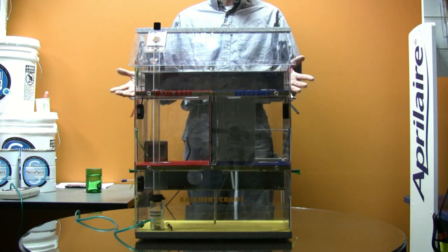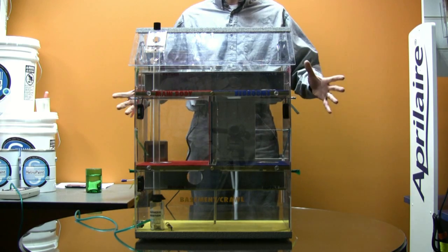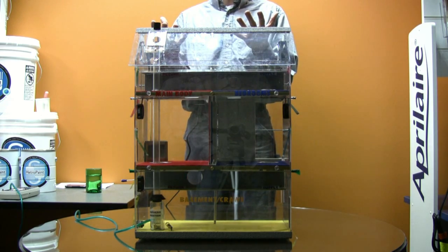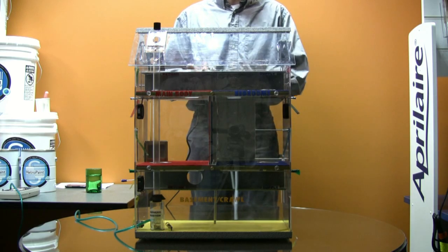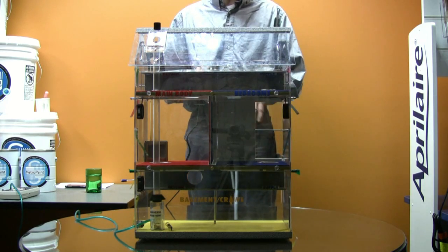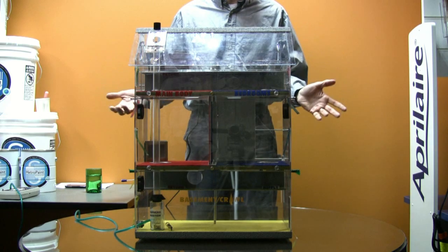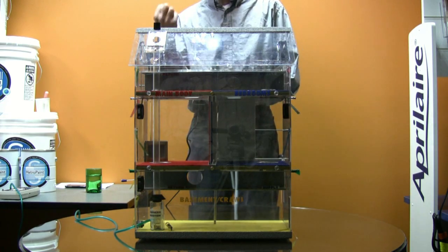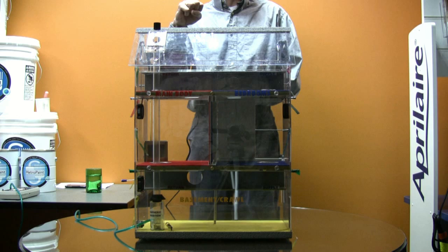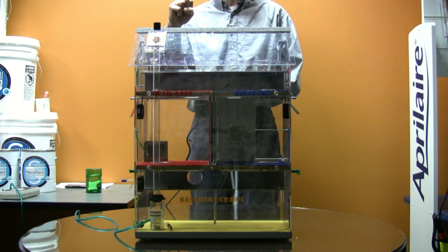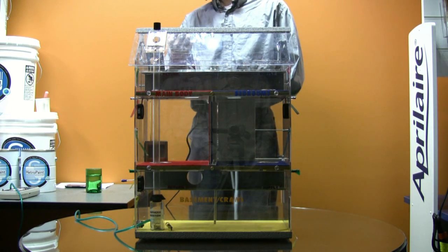You're talking 800 CFM, 1200 CFM. That's cubic feet per minute. A bath fan moves 50, 70, 90 CFM. Most range hoods might be rated at 300, and might move 150. So the power in the furnace fan to create pressure and depressurization is very large. It's a big force that you can apply to the building.